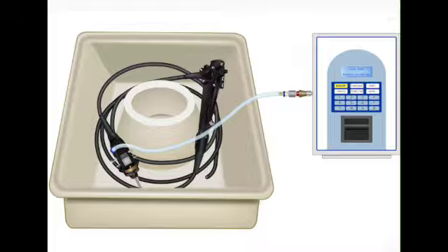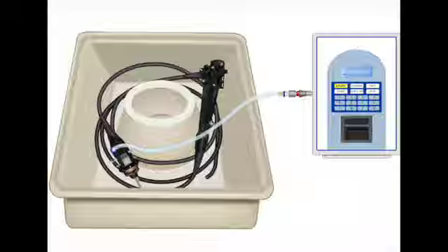Precisely. You're stressing the system. Those knobs and buttons are sealed with these tiny little O-rings. Ah, the O-rings. The O-rings are everything. They might hold pressure just fine when the scope is sitting still, but the second you turn that knob or press a button, you put stress on that seal. If it's worn, that's when the leak will show itself. So if you skip that step, you've basically done a useless test. You've done a useless test. You haven't checked the most common points of failure.